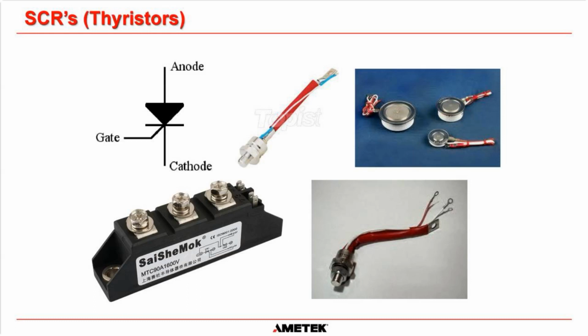We are in the process of designing and building what we call our high frequency charger, which is basically a power factor corrected charger. It's a charger that has IGBTs on the bridge instead of SCRs. That will nearly make the harmonics reflected back unity, the power factor unity. But in our experience, IGBTs are just way more sensitive than SCRs. We're going to build it and it's going to be a fantastic system, but it's just not going to be as reliable as an SCR charger.